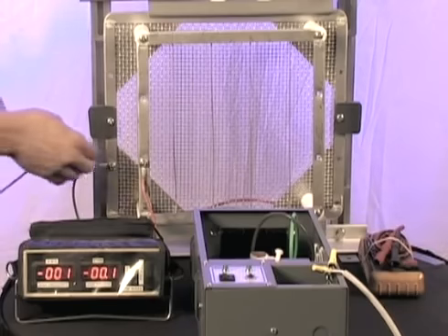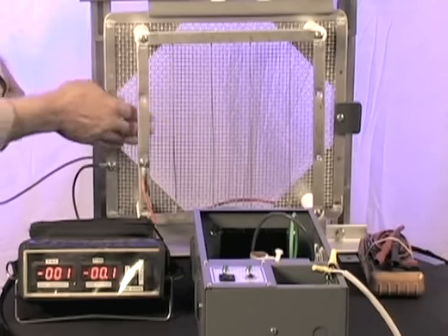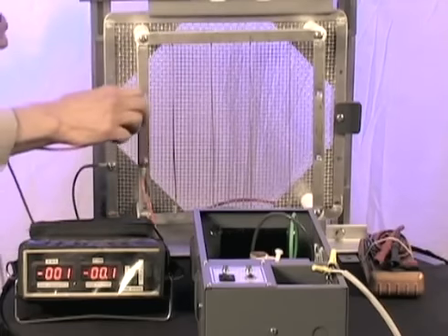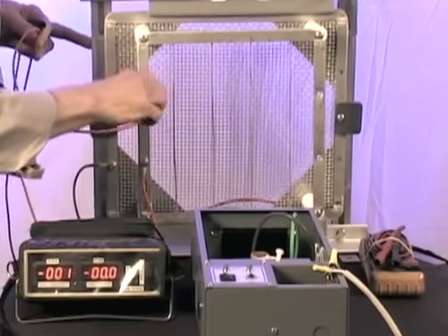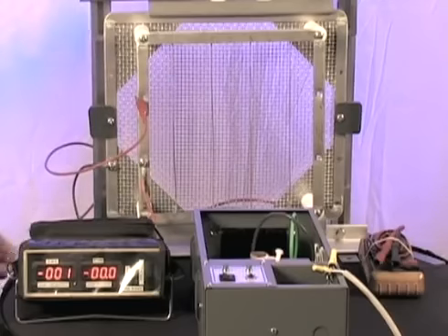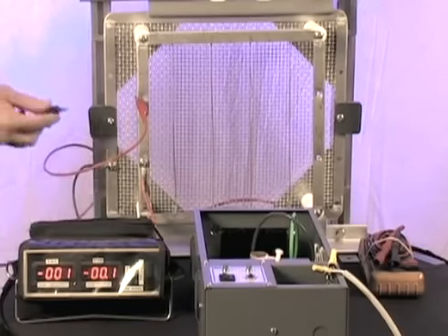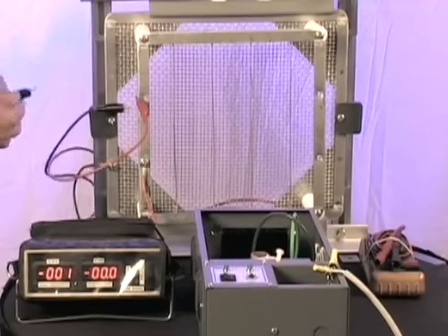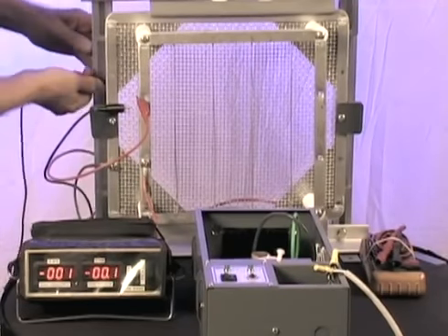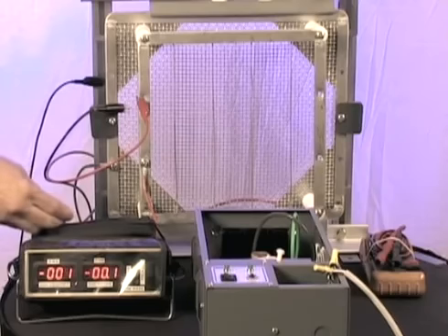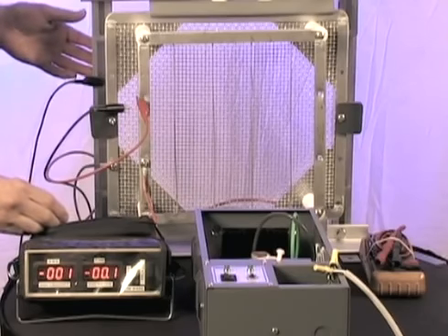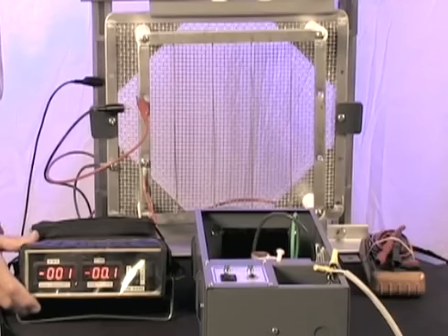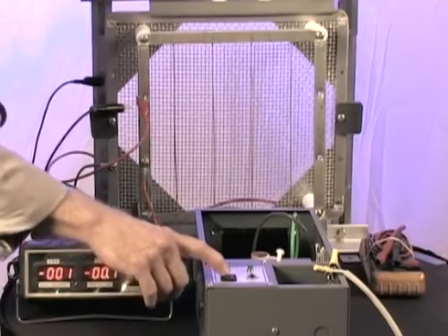The screen in the front is the high voltage, the screen in the back is the high frequency. The red wire hooks up to the high voltage screen in the front, the black wire to the high frequency screen right under the grid, and also you must make sure that your test kit is grounded to the same system ground of the system. With your test kit hooked up to the CosaTron system, restore power.